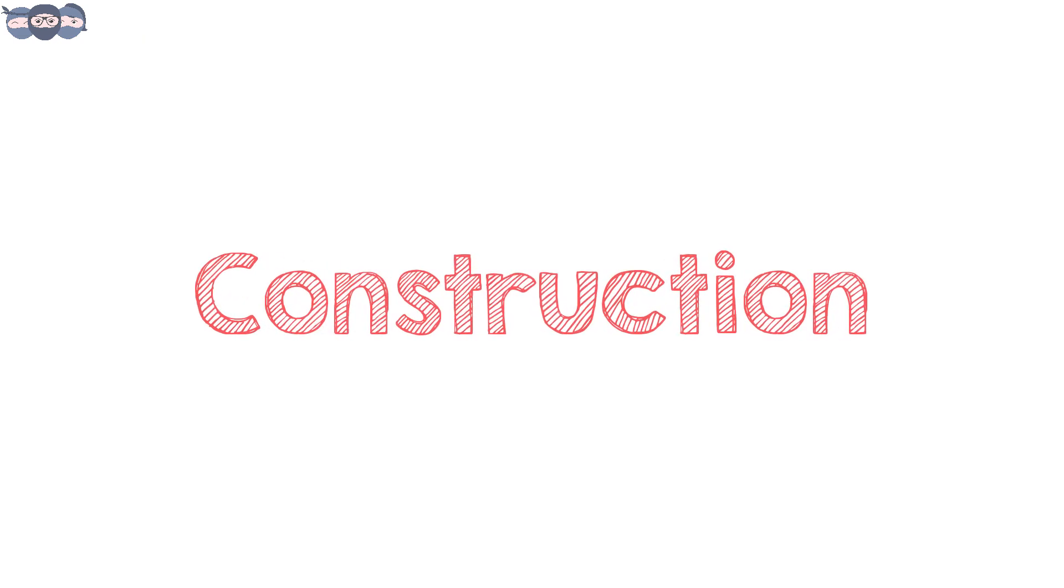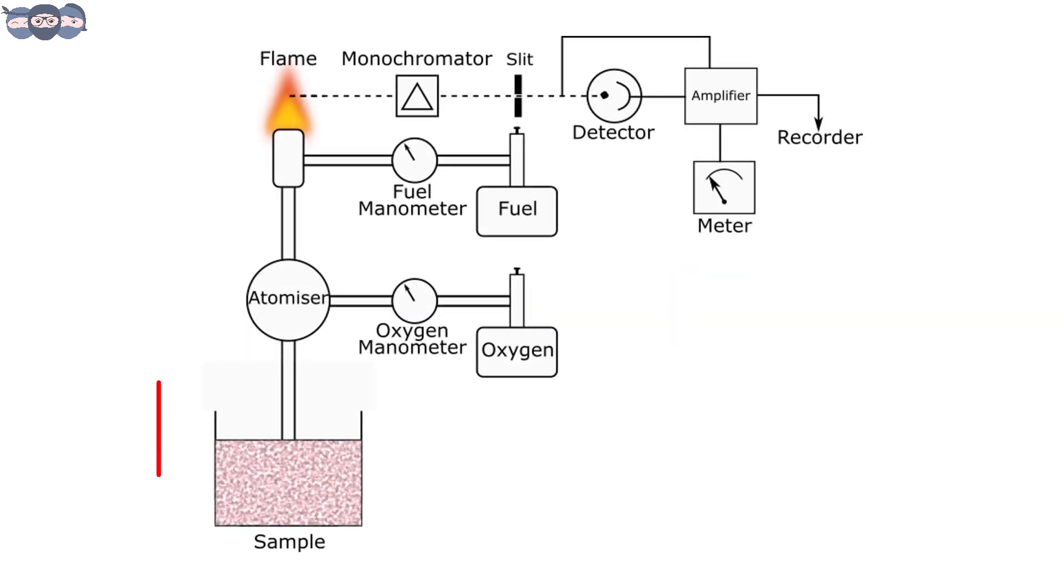Let us proceed by understanding the construction of this instrument. The first component is the sample holder. As seen here, this instrument is made up of an atomizer with flow controls for oxygen and fuel. The atomizer converts the sample to aerosol and passes this aerosolized sample to the next unit.